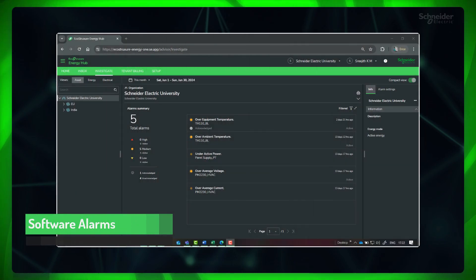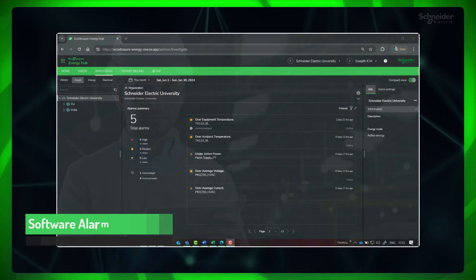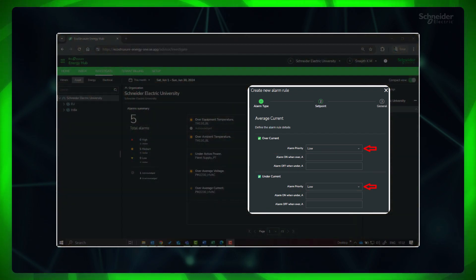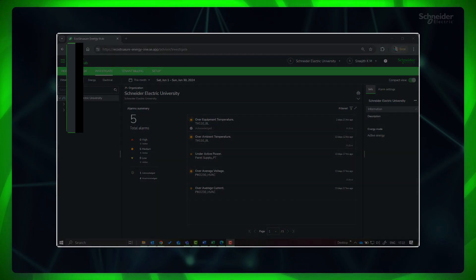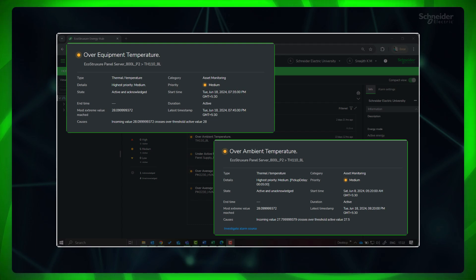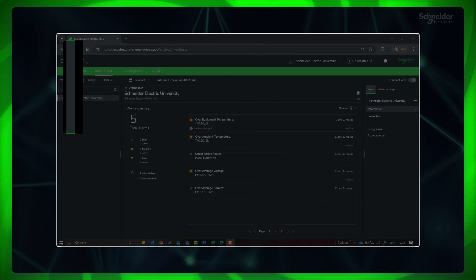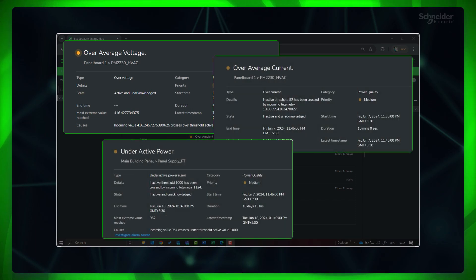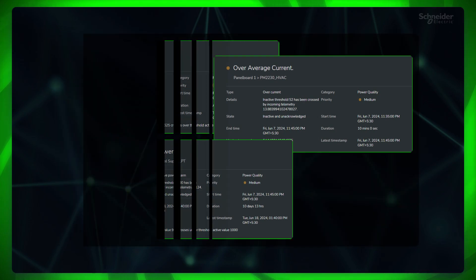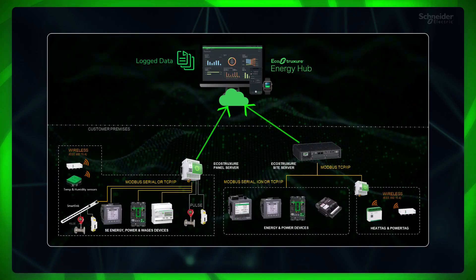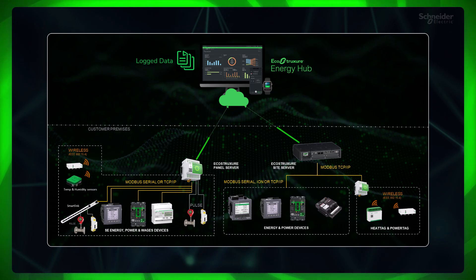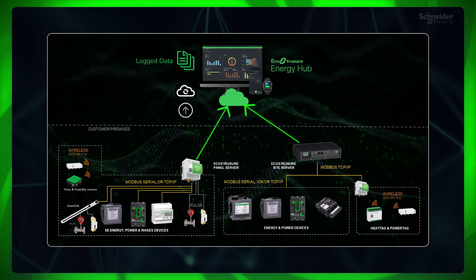Next are software alarms. These alarms are configured in Energy Hub by the user with the required thresholds and priority, for any supported devices or elements in the hierarchy. These include equipment and ambient temperature alarms, which fall into the category of asset monitoring, and average voltage, average current, active power, and power factor alarms, which belong to the category of power quality. These alarms use logged data, so the evaluation period taken by Energy Hub to check the measured value against the thresholds depends upon the gateway publication interval.